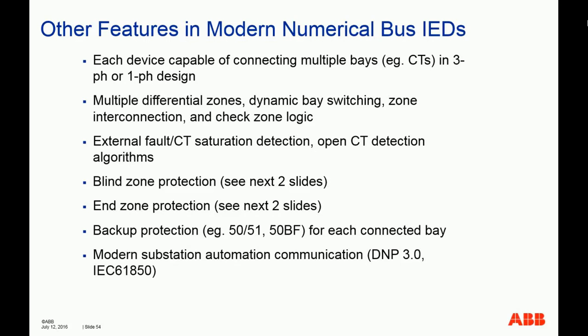And we talked about the external fault or CT saturation detection through the graphical representation. Blind zone, end zone, we'll talk about it in the next two slides. Backup protection: modern numerical bus relays all should be equipped with bus backup protection such as overcurrent, one for each feeder, and breaker fail protection, one for each feeder.